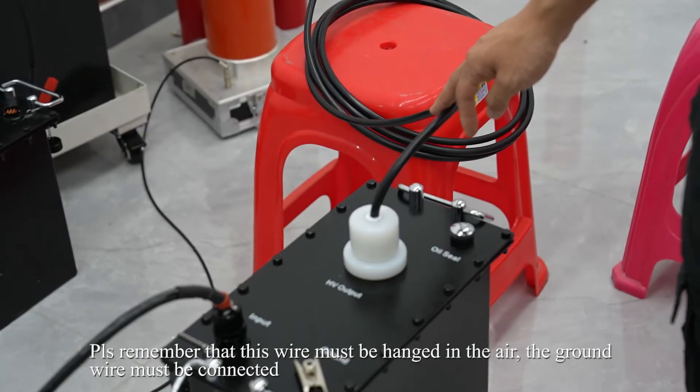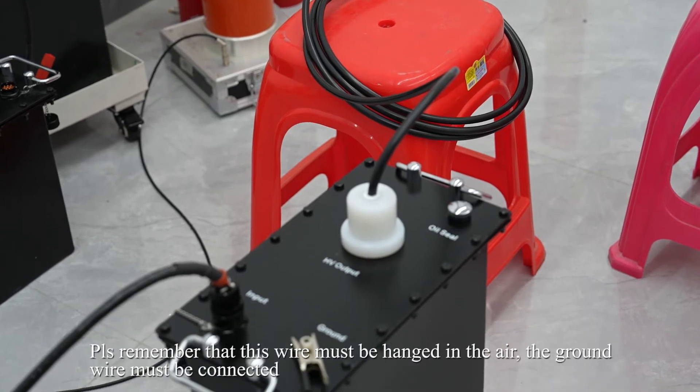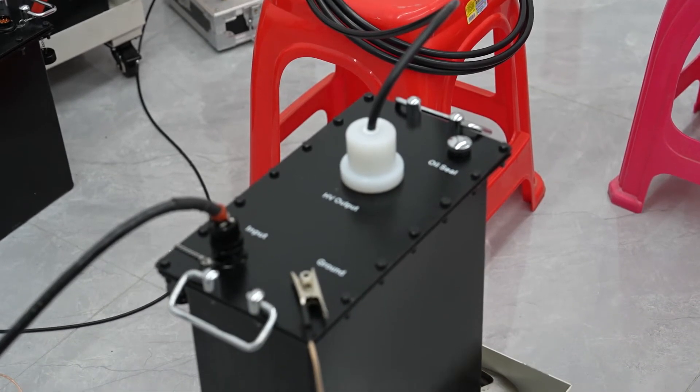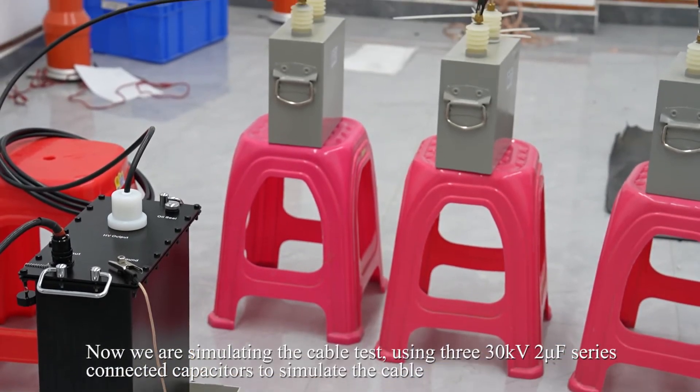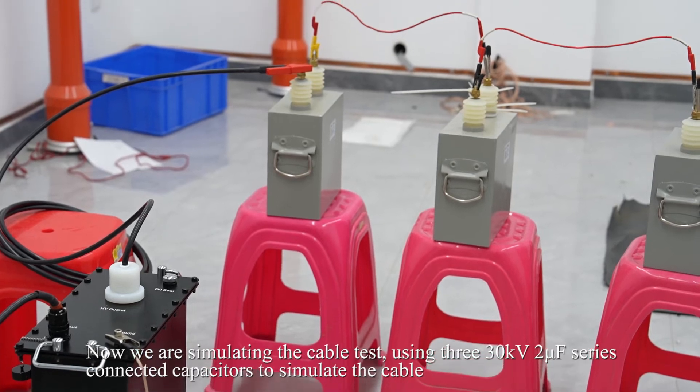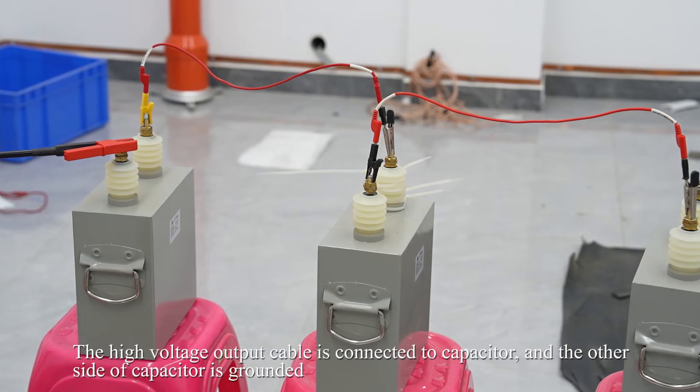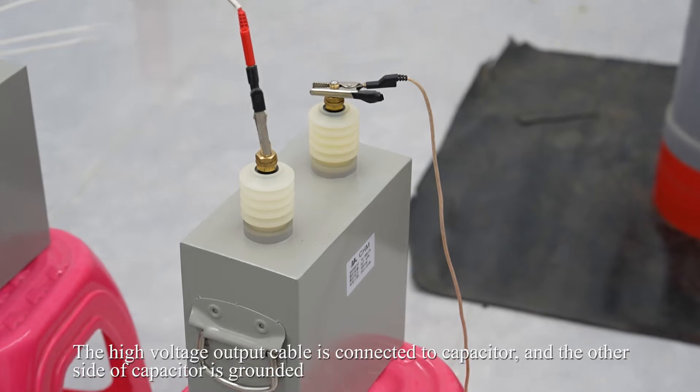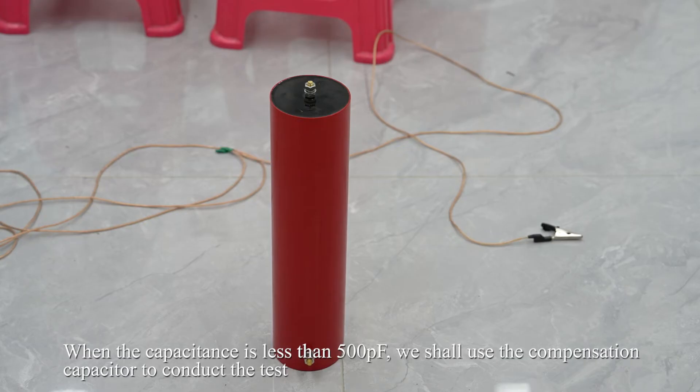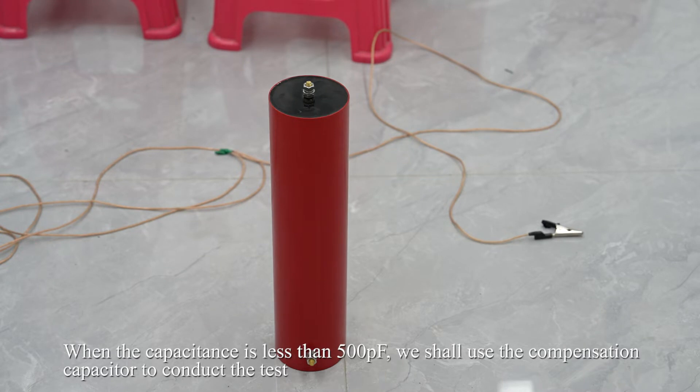Please remember that this wire must be hanged in the air. The ground wire must be connected. Now we are simulating the cable test. Use 3 pieces 30KV 2µF series capacitors to simulate the cable. The high-voltage output cable is connected to capacitor, and the other side of the capacitor is grounded. When the capacitance is less than 500 pF, we shall use the compensation capacitor to conduct the test.